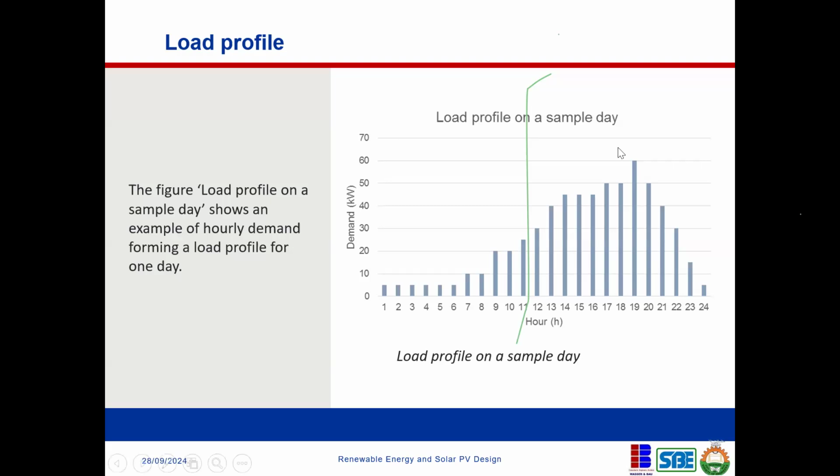So, okay, this is what your peak demand looks like. But again, I can advise you to implement some level of load management. So whenever you're running your generator, please don't turn on this load at that crazy peak. If you ever want to use this equipment, please use it at any of these times. So instead of recommending a 60 kW load, which will be about an 80 kVA generator, you can recommend a lower capacity generator, which will save capex and lower fuel consumption. But again, it has to come with load management. You have to find a way to shift your load, so you can move your peak load to these valleys.